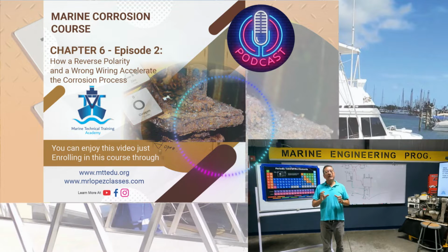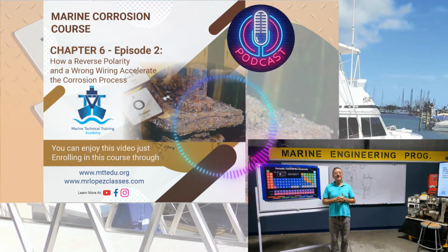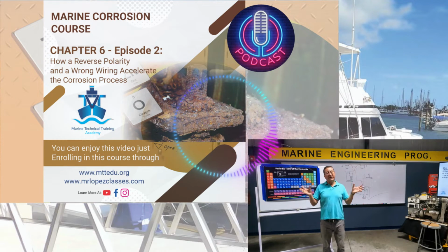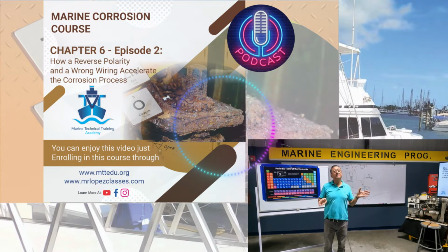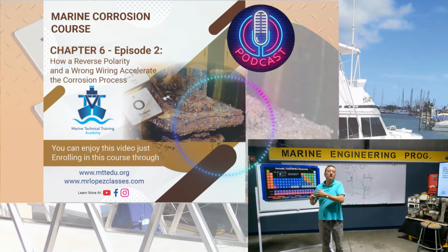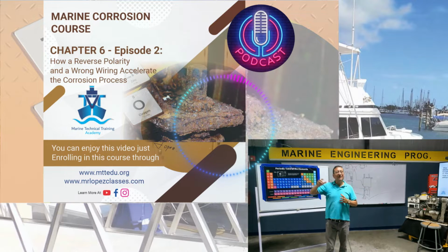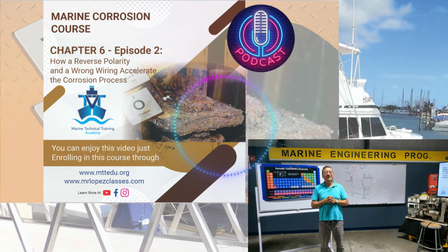If you have your multimeter, select volts AC, and check the voltage between hot and neutral, and after that between hot and ground, and copy the values.